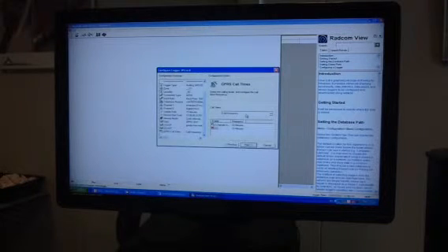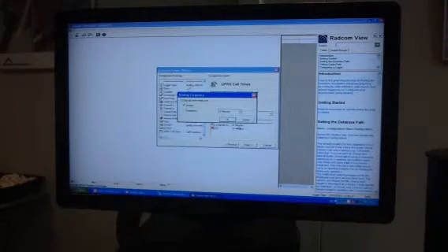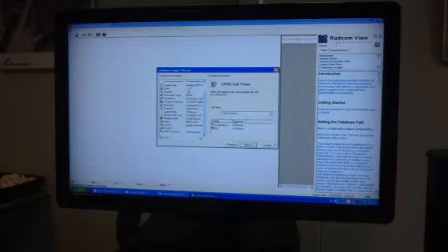Call frequency: you can have anytime you would like your logger to call in. At the moment it's defaulted to 15 minutes, but you can change that to anything you require. 15 minutes, make sure it's enabled and press OK. Then this takes the cross out of the box so it shows it's active.